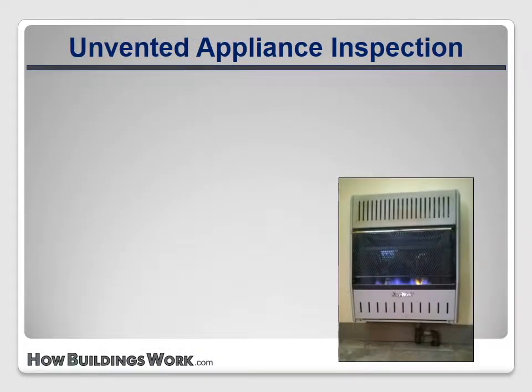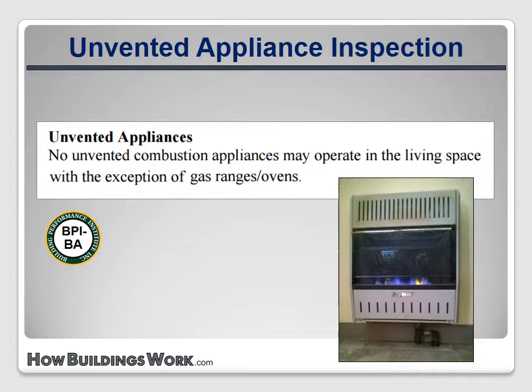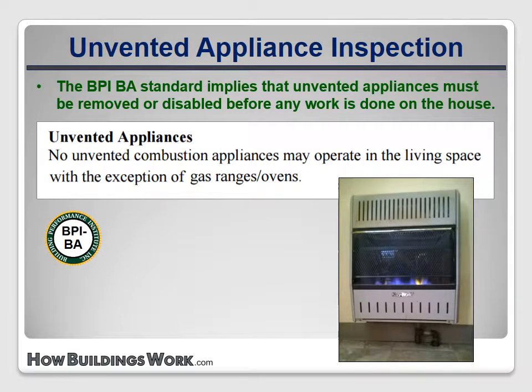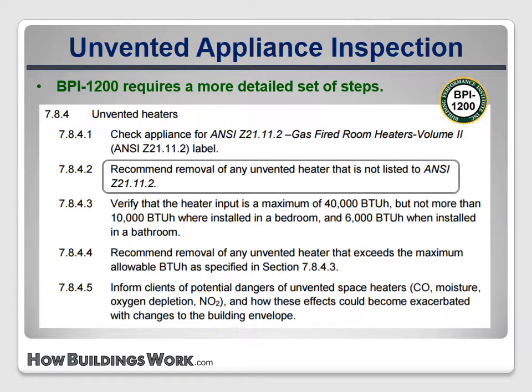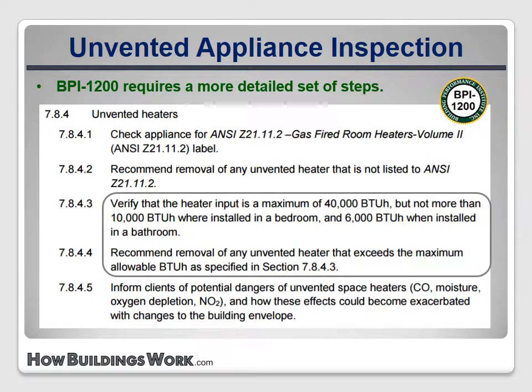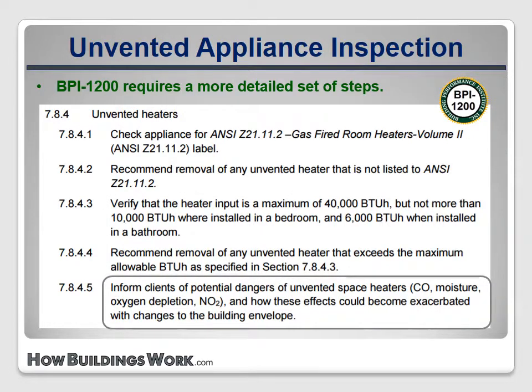BPI 1200 and the BA Standard address unvented heaters very differently. The BA Standard implies that these appliances must be removed or disabled if weatherization work will be done. BPI 1200 takes a more systematic approach — it requires recommendation of removal of any unvented heaters not listed to ANSI Z21.11.2, which requires an oxygen depletion system. It also requires recommendation of removal of models larger than 6,000 BTUs per hour in bathrooms, 10,000 BTUs per hour in bedrooms, and 40,000 BTUs per hour in other areas. BPI 1200 also requires that auditors inform clients of the potential dangers of these heaters and requires testing of them.